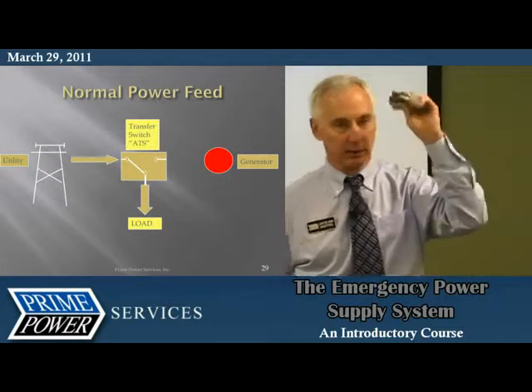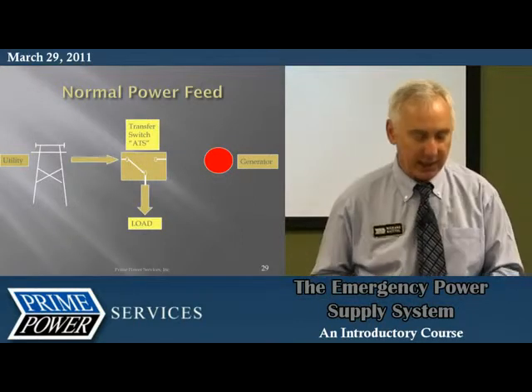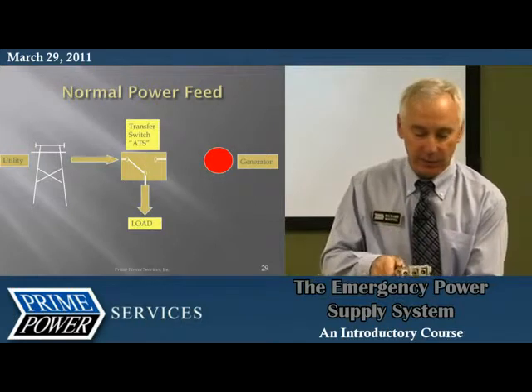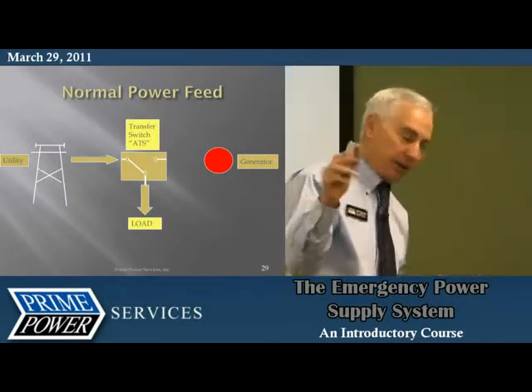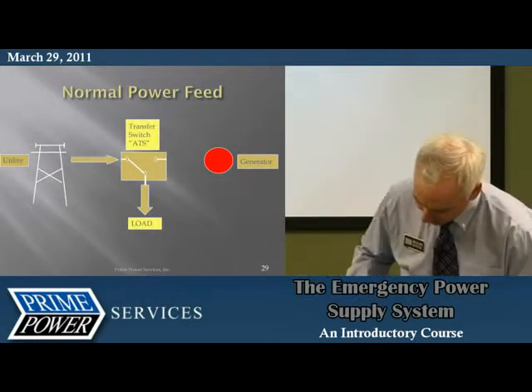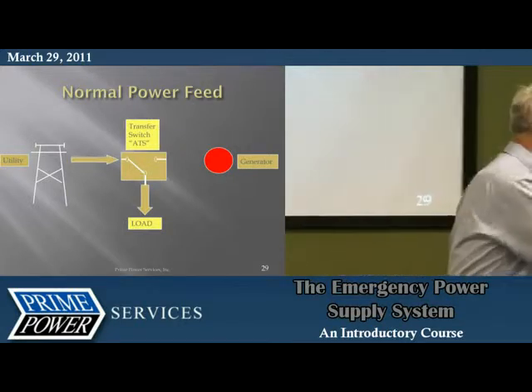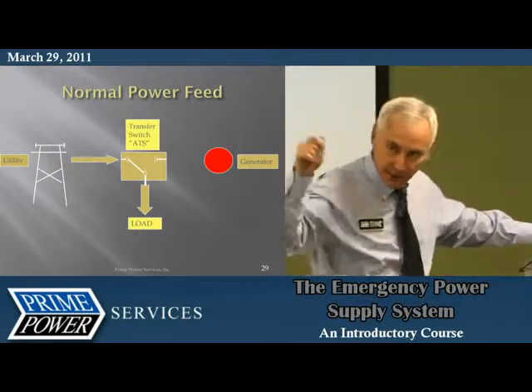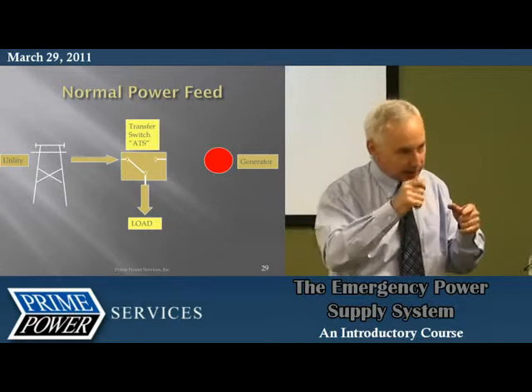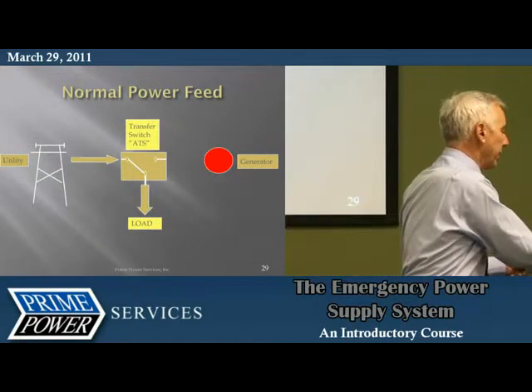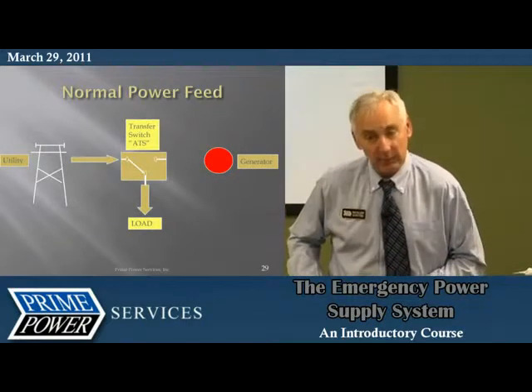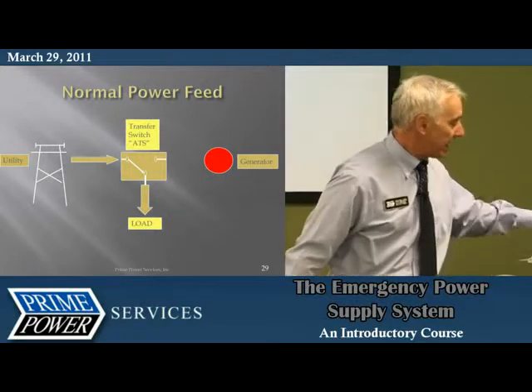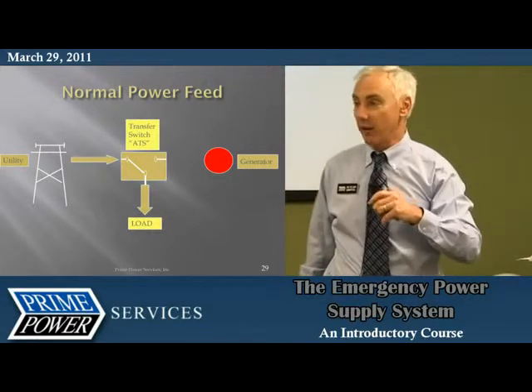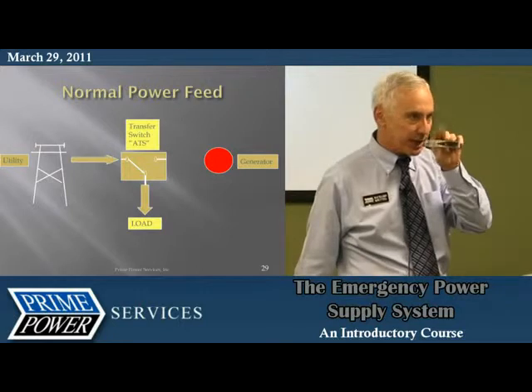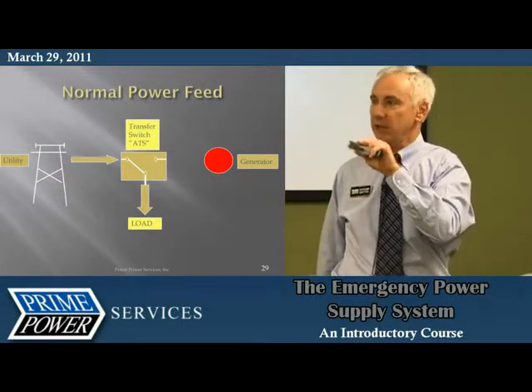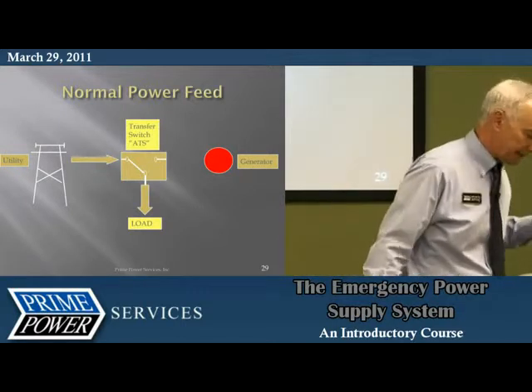This particular thing here is called an arc chute, and that fits over the top of the contacts. We've got a 3-pole switch, A, B, and C. On this C phase, this arc chute, what happens when it opens, if there's a whole bunch of load on it - any of you guys that have held a welder in your hand and struck the arc and pulled it away, it's drawing an arc, that's where we start melting the steel to weld. Same thing happens here. If there's a big load on it, the minute it opens there's an arc. That arc spreads, and as it spreads it gets cut up into small sections through this arc chute. So this arc chute is designed to extinguish that flame going on inside of this thing.